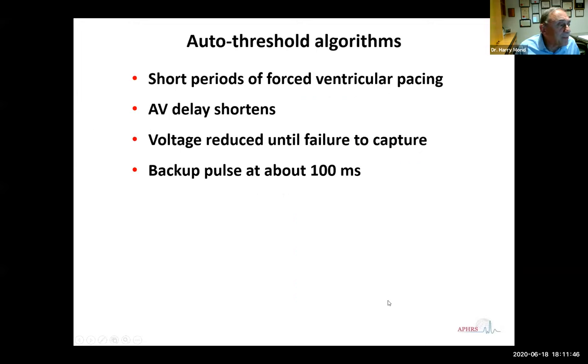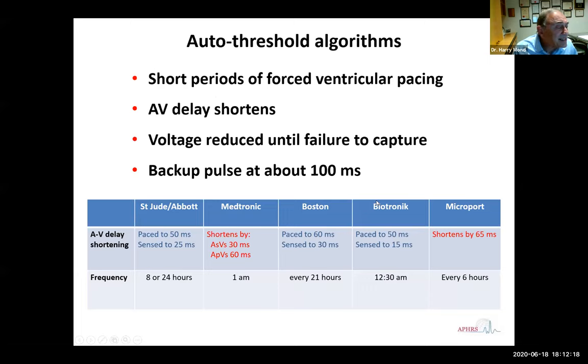The last one I'd like to talk about are the auto threshold algorithms. These are short periods of forced ventricular pacing that you see on an ECG or a Holter monitor. During these periods, the AV delay shortens, and for each beat, the voltage is reduced until there is failure to capture. There is then a backup pulse at about 100 milliseconds. Most of the companies have similar algorithms, but there are two basic differences that you can see on the ECG. Some of them shorten the AV delay to something like 50 milliseconds, whereas others shorten it by a small amount.